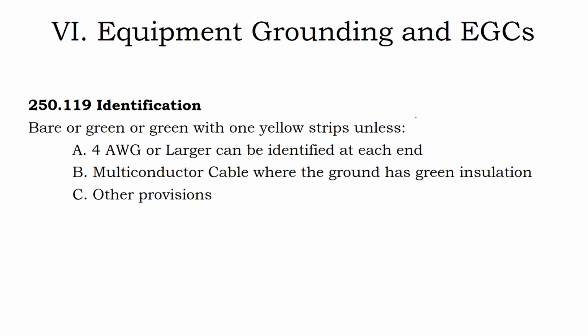In terms of running equipment ground conductors, it has to be either bare or green until you get into larger cable sizes. Once your cable sizes become sufficiently large, you can just use black cable and tape it. But if you're in like number 6 or number 8, and you're putting a jacket all around that cable, then it has to have green insulation. I think that using colored jackets on your cables looks really good and helps out the crew. On the solar end of things, you can get a red and a black jacket for your positive and negative cables, and it just helps keep things clear.